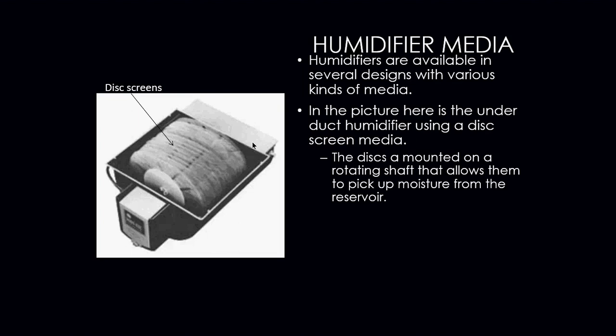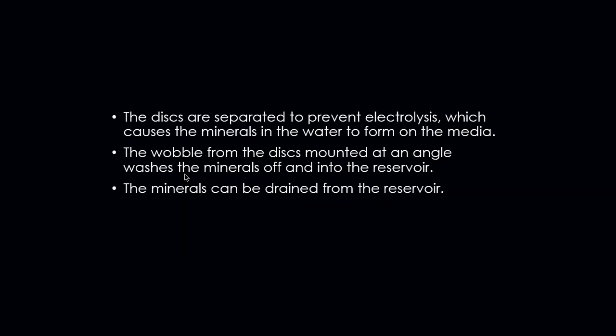Your media filter has several different designs. Okay, and this picture here is the underduct humidifier, and that's using a disc screen type media. And these discs are mounted on a rotating shaft that allows them to pick up moisture from the reservoir. Now, these media filters that are in here, these things are going to get dirty. These have to be replaced on, like I said, a yearly or even a monthly basis, depending on how much the humidifier is being used. Okay, the discs are separated to prevent electrolysis, which causes the minerals in the water to form on the media, and the wobble from the disc mounted at an angle washes any minerals off and back into the reservoir, which is why we have to maintain them.